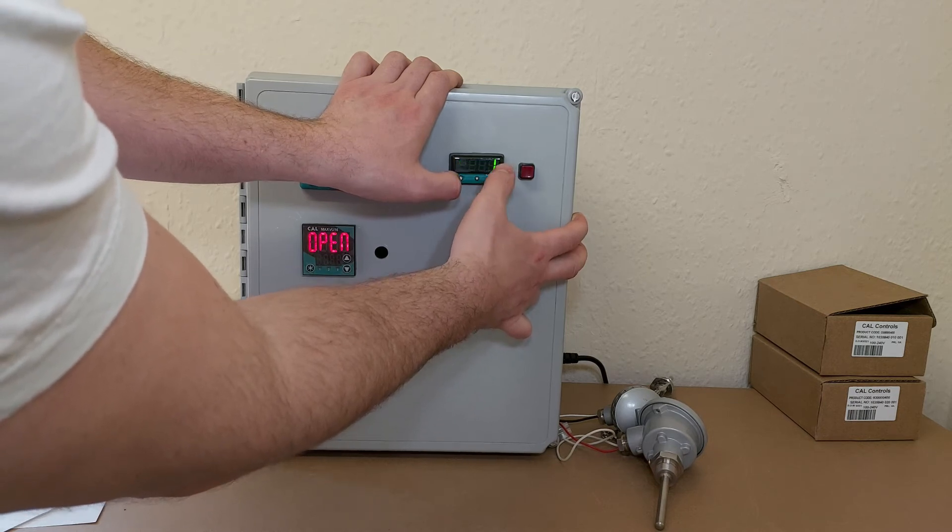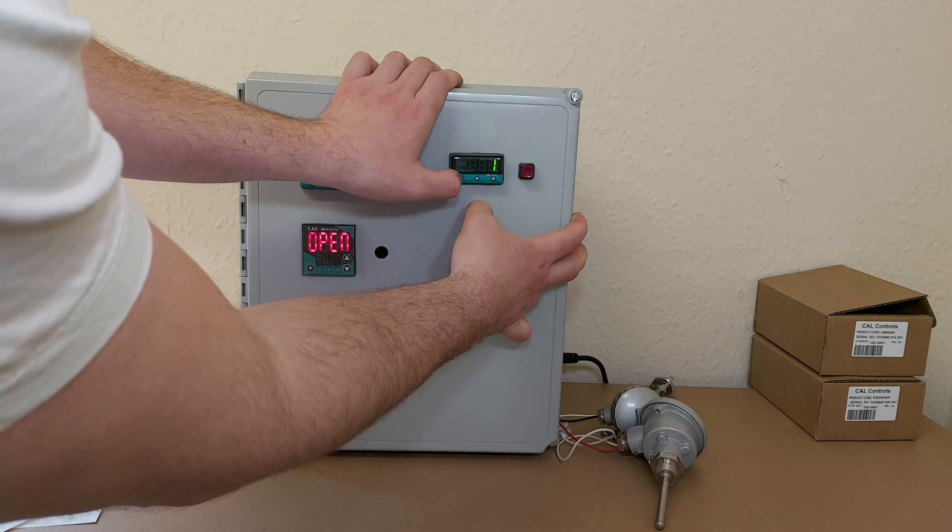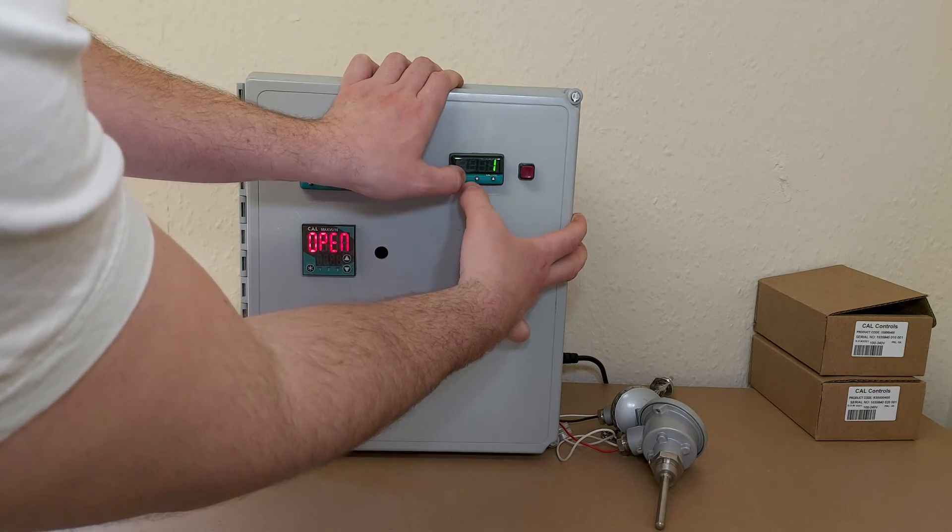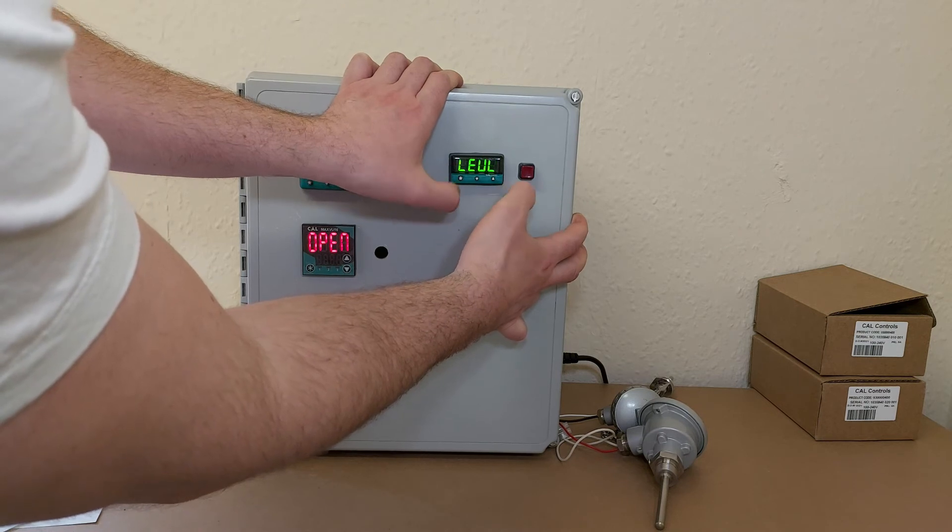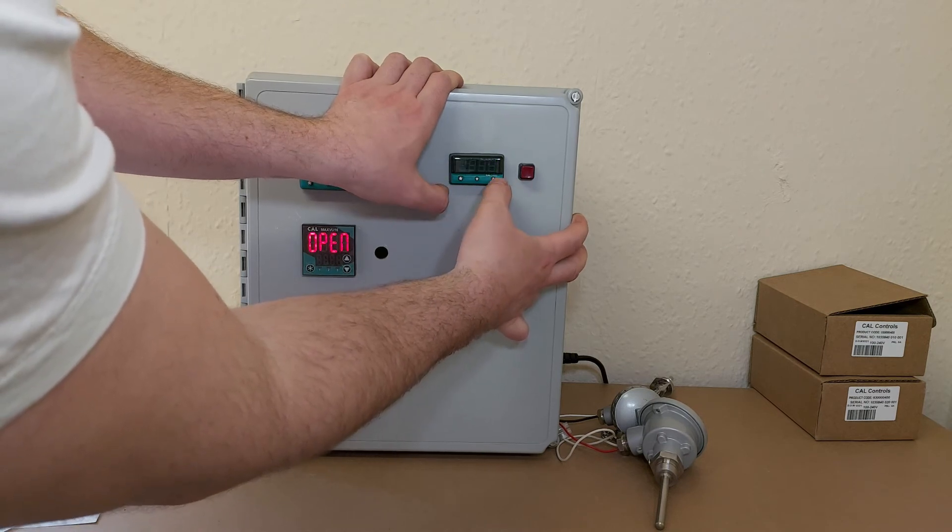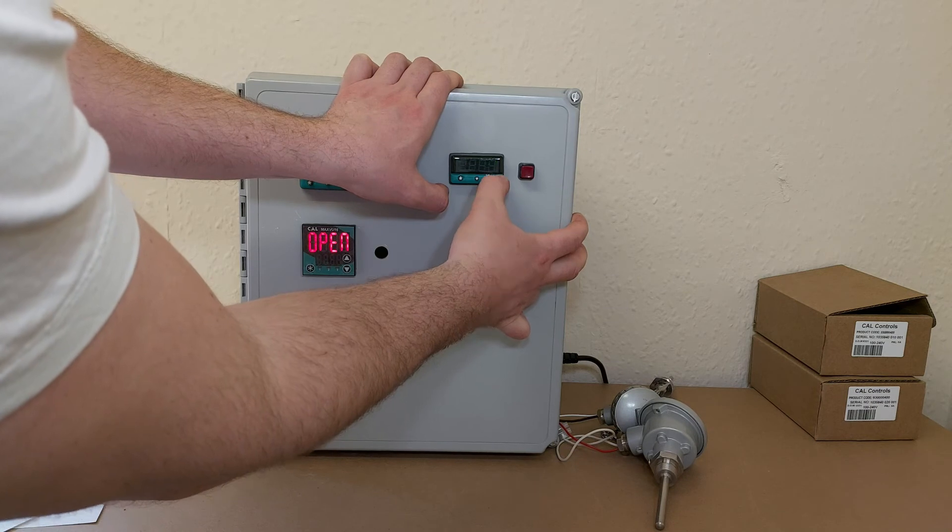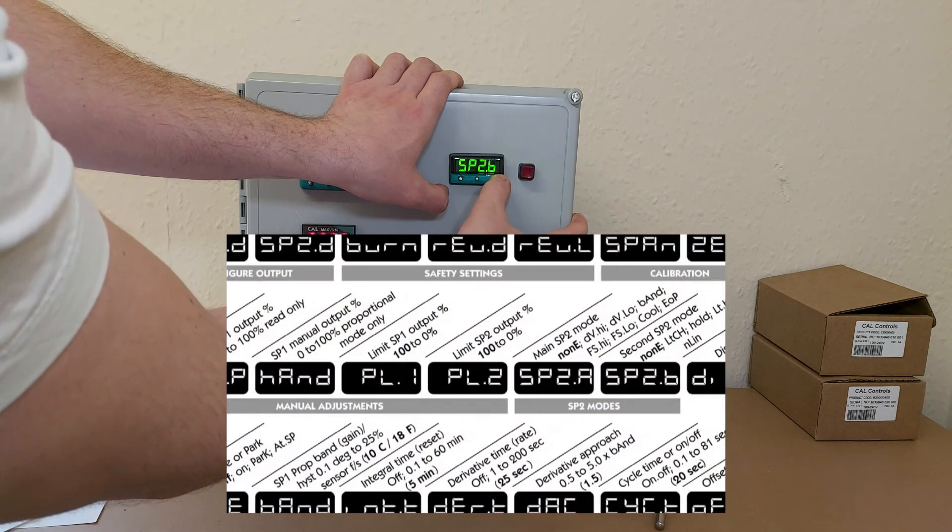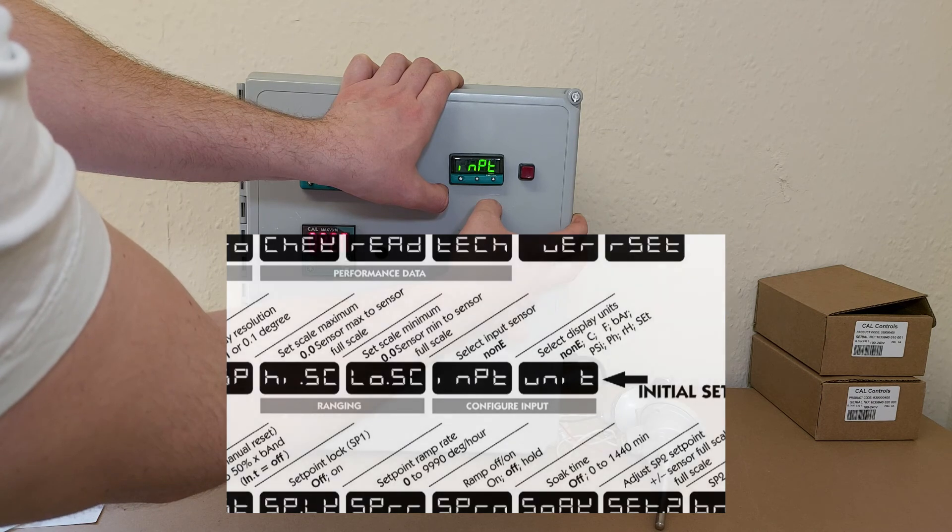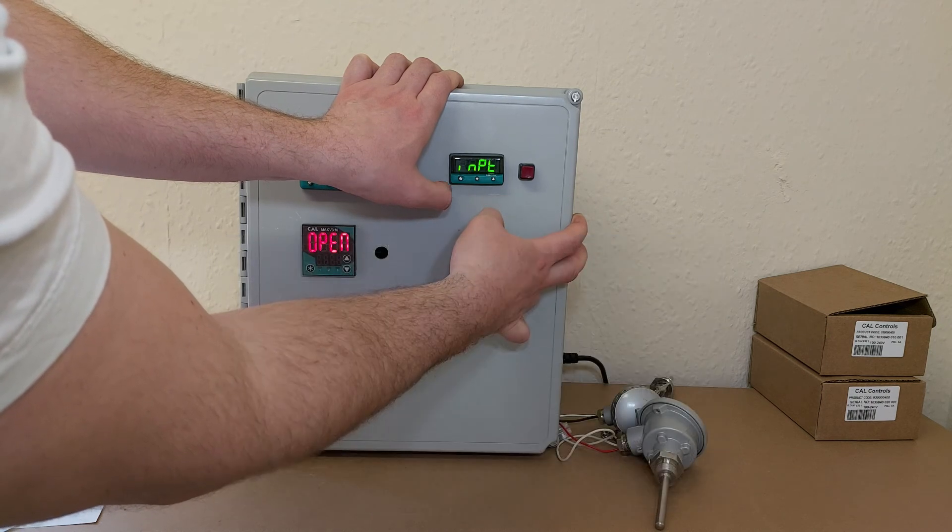And we are at level one at the moment. We want to go into level two by holding the star. Going up to two. And now we can scroll through the level two menu until we get to input. There we are. And we want to select RTD and it's set up for RTD already.